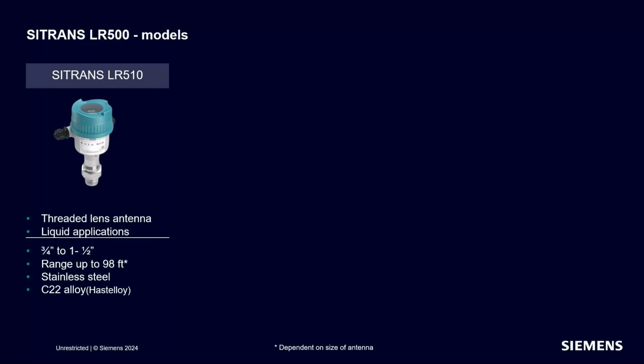To summarize the 500 series, the 510 is designed for liquid applications. It has a threaded process connection, I think the minimum is 3/4 of an inch. They're available in stainless steel, and for harsh chemical applications, you can get them in C22 alloy, Hastelloy. The lens antenna material is PEEK, and the seals are available in FKM or FFKM. Again, ADSs, application data sheets, when provided to your sales rep, will tell us what's in that tank and help us choose the proper materials of construction to make sure these transmitters last as long as possible in the application they are installed in.